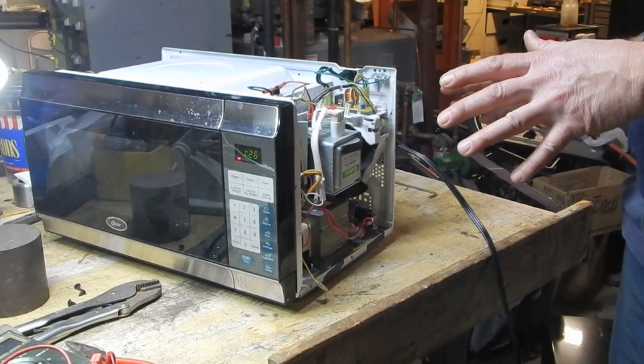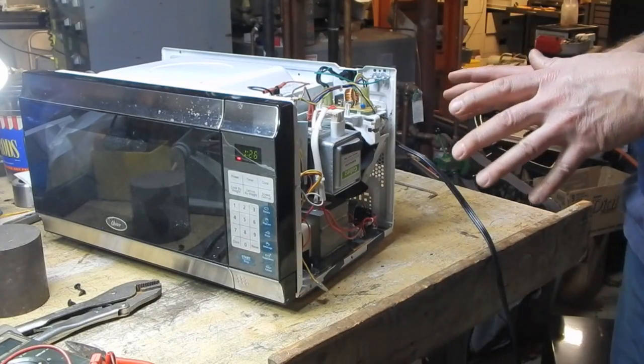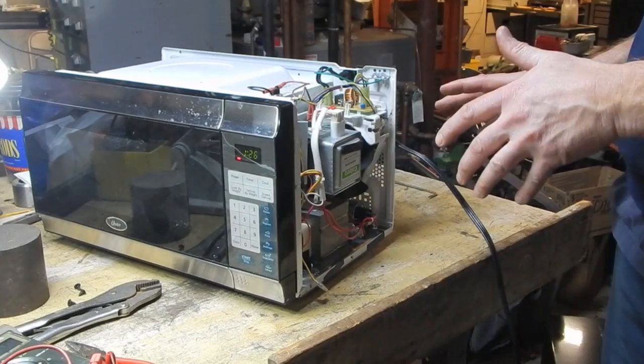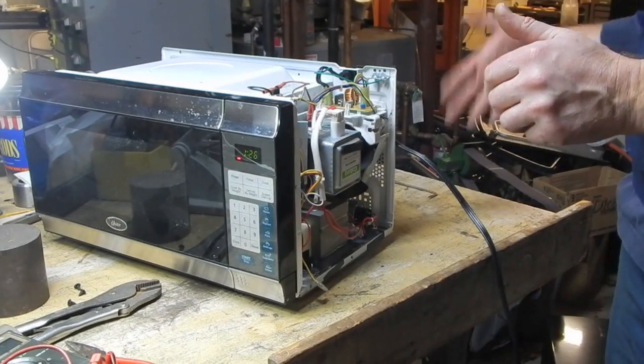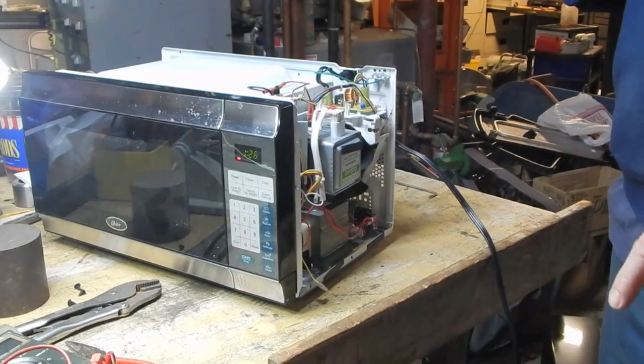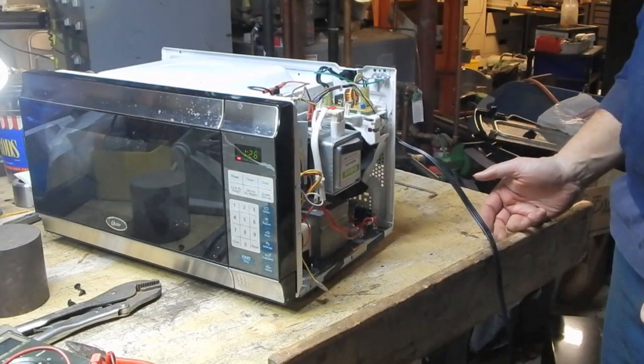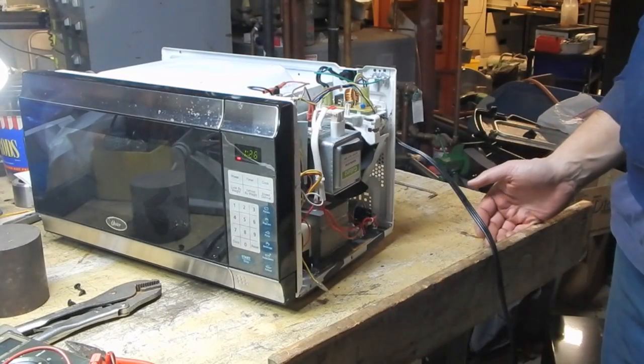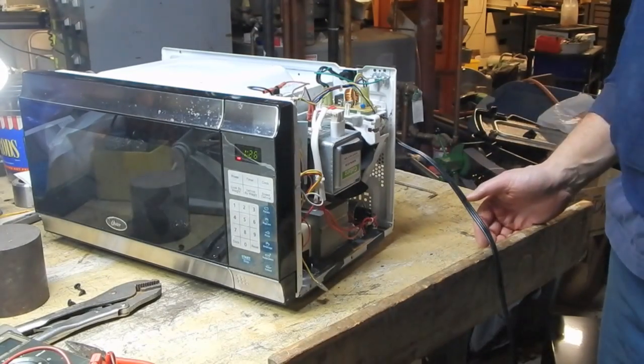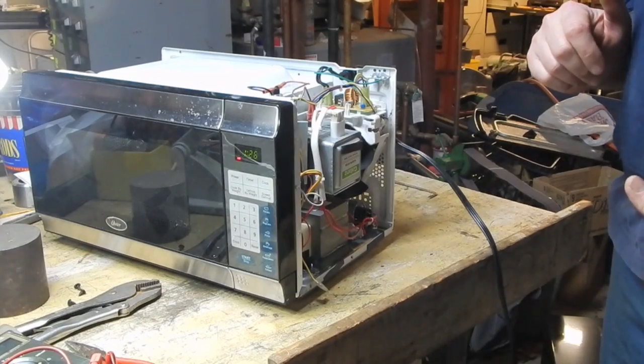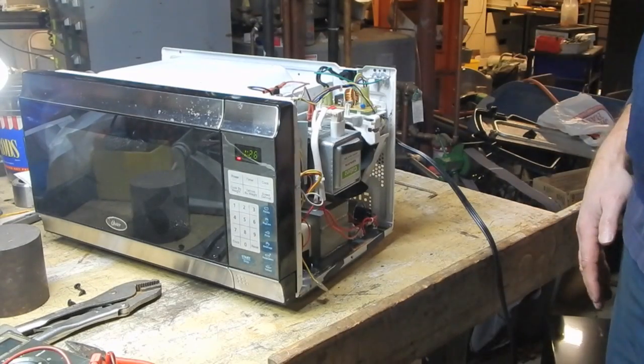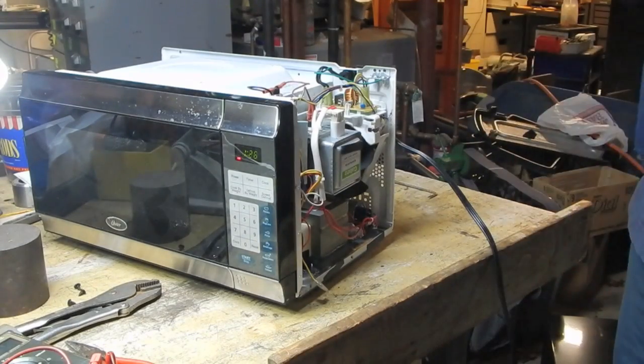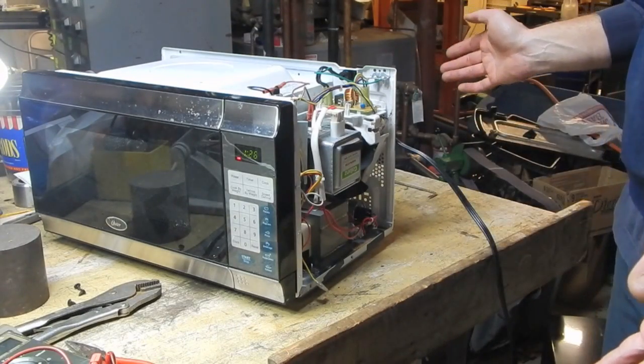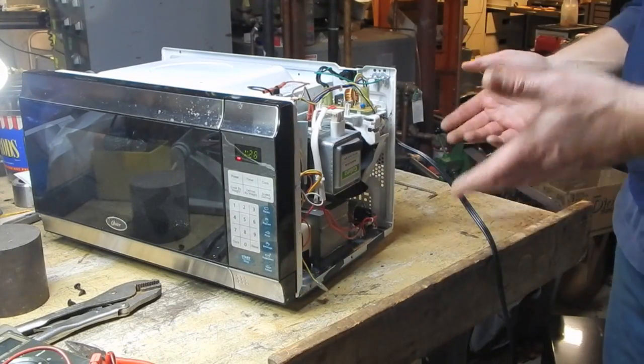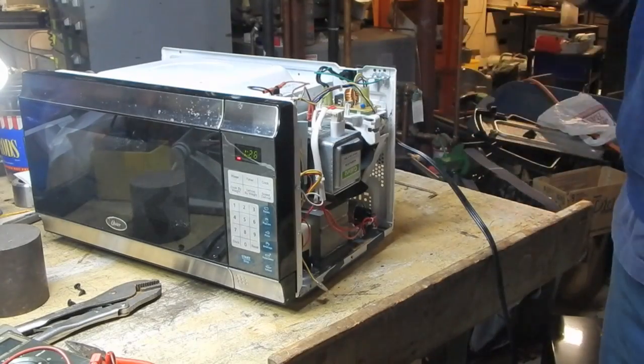Or maybe while the microwave was running and somebody was cooking something, there was a transient voltage event of some type coming in through the line, and the voltage went a little high, which caused the current to shoot up, and the fuse popped and basically protected everything. Because sometimes you just get one of those fuses pop, you put a new fuse in, and everything's good to go. Now if the fuse keeps popping, well, obviously if it blows immediately, you know you've got a dead short.